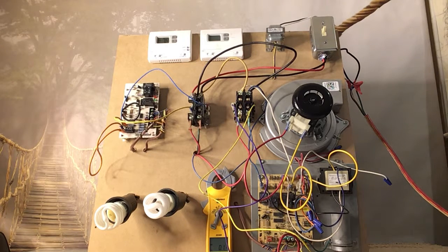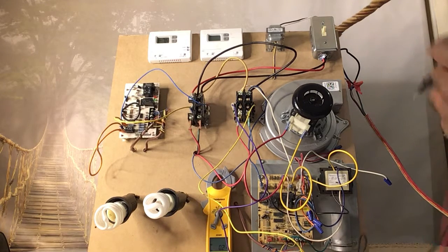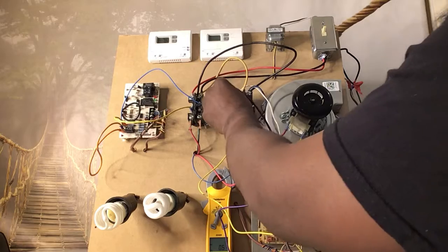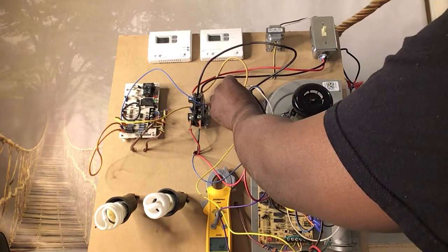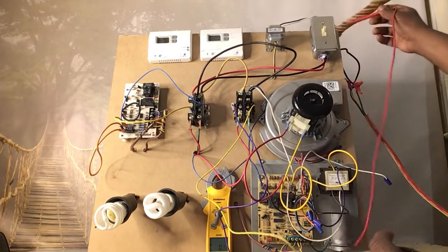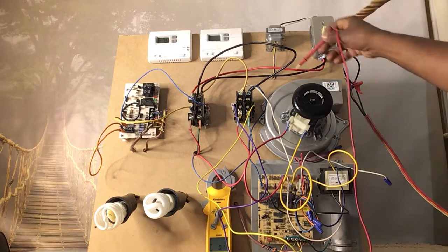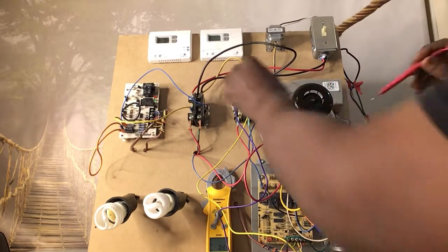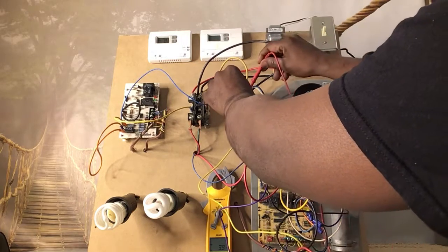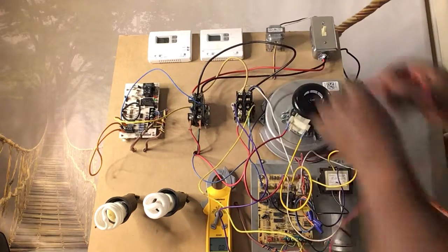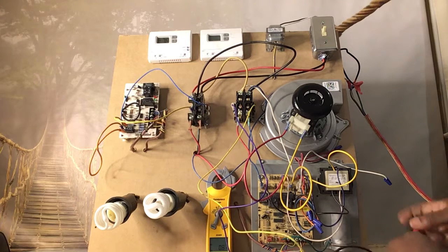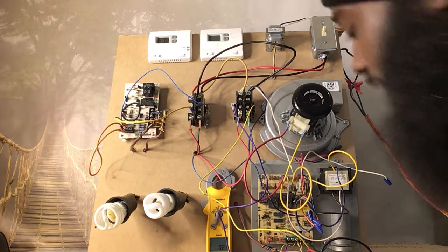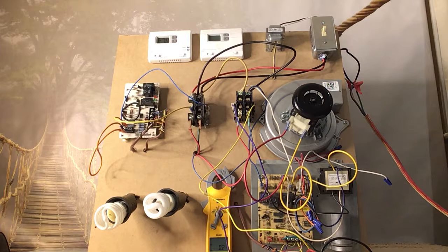So first off, my stat is not lit, so I can already assume that we are probably having some voltage issues. What I'm going to do is just check voltage. This voltage right here, I know for a fact once the switch is on, comes directly, so it should be hot once the switch is on, and it should read 115 volts. So already we got some troubleshooting going on. Give me one second and let me check the power source we are on.